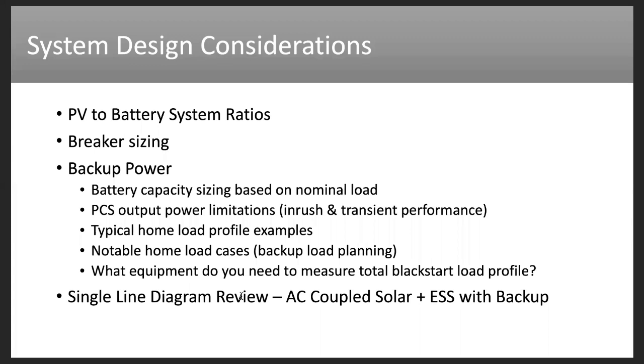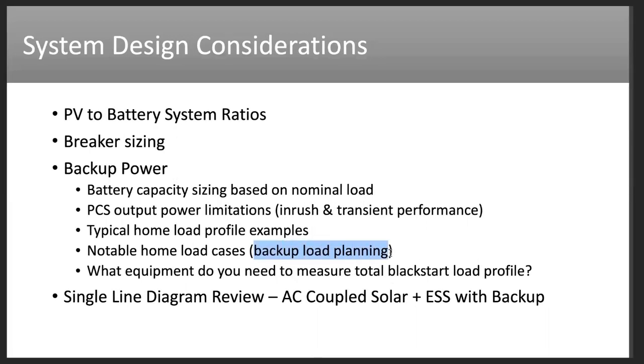And I think that for those of you who may choose to take the RENVU services as a part of your battery installation program, some of this may be taken care of by RENVU. But as a review anyways, what we're going to cover here is PV to battery system ratios, breaker sizing, and backup power, some of the battery capacity sizing based on the nominal load, the PCS output power limitations for inrush and transient performance, typical home load profile examples, notable home load cases, and really importantly, backup load panel planning.